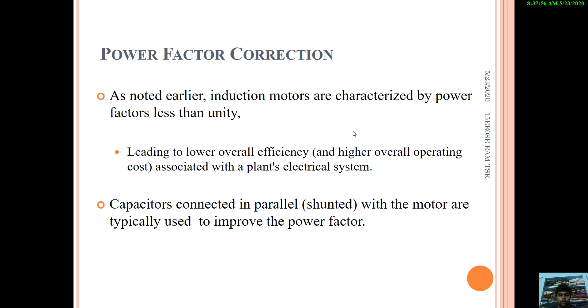The impacts of power factor correction include reduced kVA demand, reduced I2R losses in cables upstream of the capacitor, reduced voltage drop in the cables, and an increase in the overall efficiency of the plant electrical system.